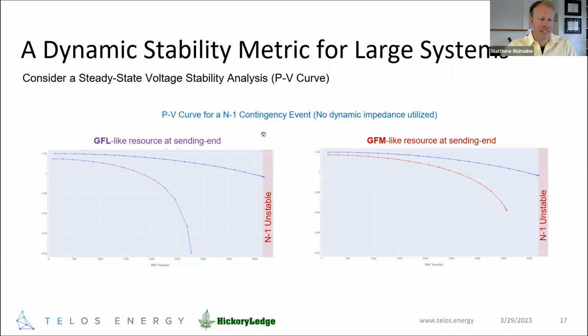Now, if we introduce that dynamic impedance and consider two of the example resources, on the left in purple we have a grid-following-like inverter resource at the sending end. Introducing that dynamic impedance has a pretty substantial impact on the shape of this PV curve, in that for lower levels of active power transfer, voltage is not supported as well.